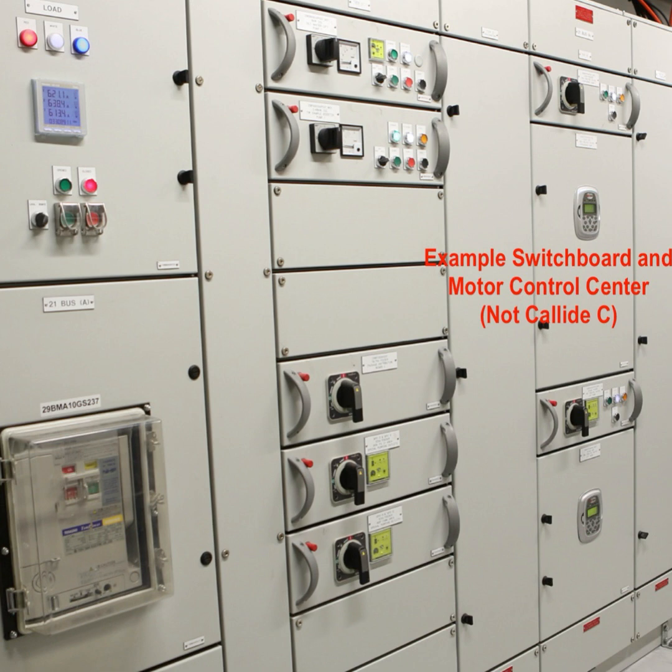At home, when we unplug some electrical appliances on the wall, larger devices with large capacitors will continue to illuminate the power LED on the appliance for several seconds after being disconnected, whereas other, smaller appliances for perhaps only a fraction of a second. In this case, the 220-volt DC system was huge, and the battery chargers were huge as well, and hence the decay of the DC bus voltage took longer than you might expect. But this wasn't the only factor. Since the station DC battery charger was outputting a higher voltage, the Unit C4 battery charger had already started ramping down its output voltage in response, giving the load to the station charger per its output setting.